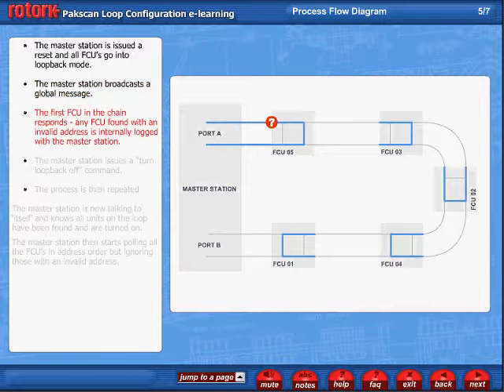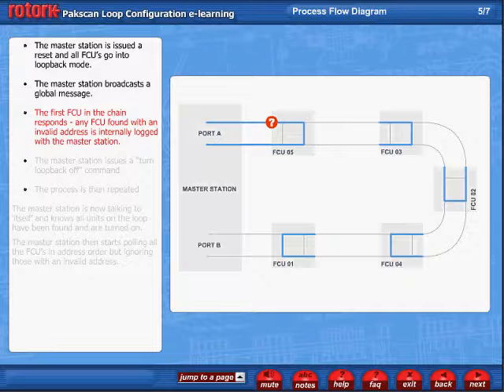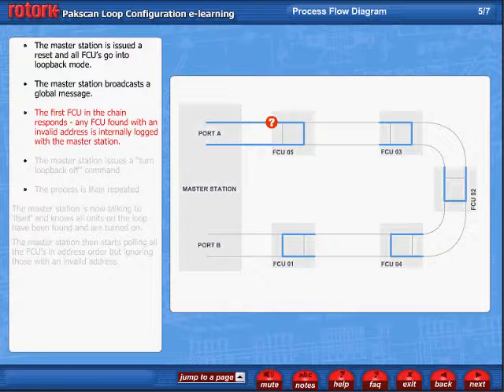The first FCU in the chain responds by giving its address, and the master station checks to see that this is a valid address and builds a position against an address map. Any FCU found with an invalid address will be logged internally within the master station and used to give a fault indication to the operator.